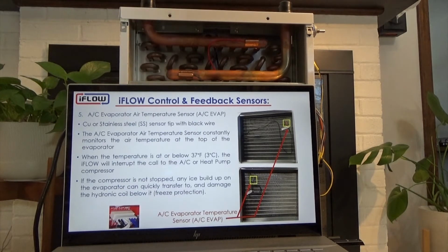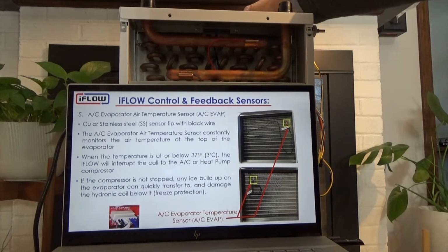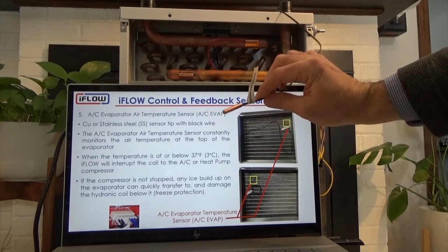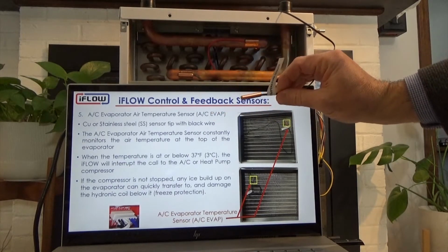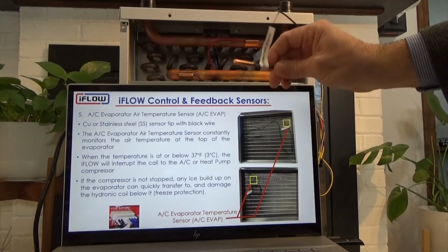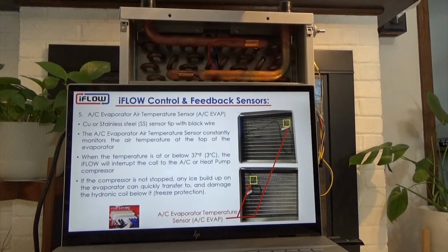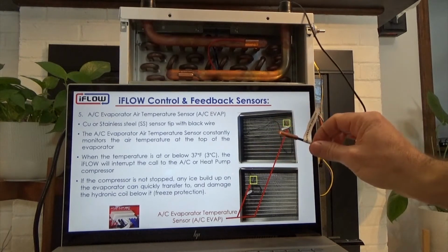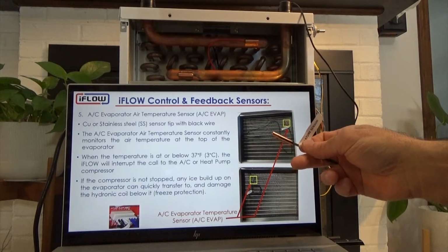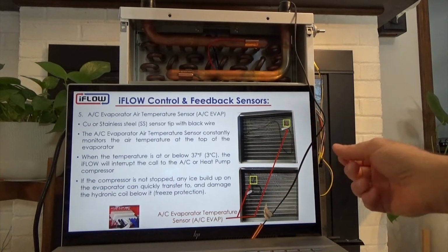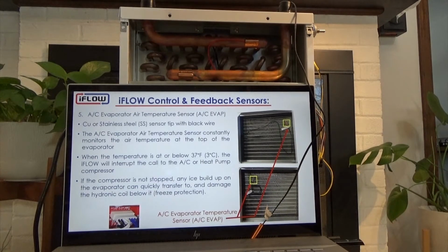The AC evaporator temperature sensor, as I mentioned, can be in copper or in stainless. The settings are the same, the capabilities are the same, just different models. It's reading the temperature coming off the top of the evaporator coil continuously, and it will be strapped to the top of your evaporator. When it sees a temperature of 37 degrees Fahrenheit or 3 degrees Celsius or below, it is going to interrupt the call to the AC compressor.